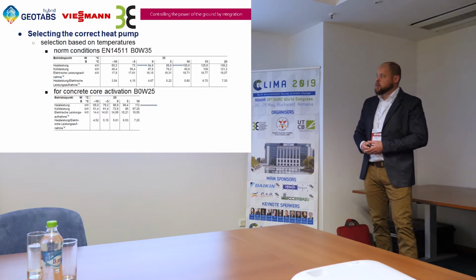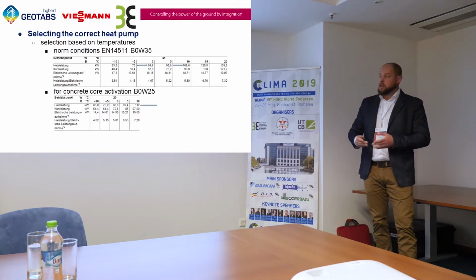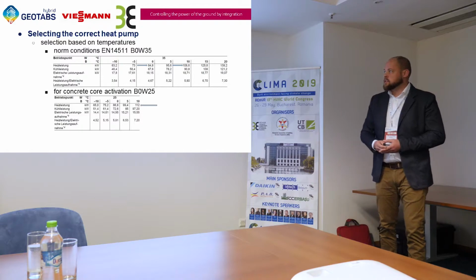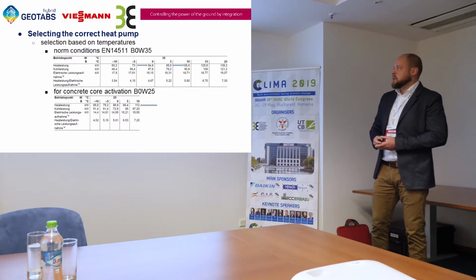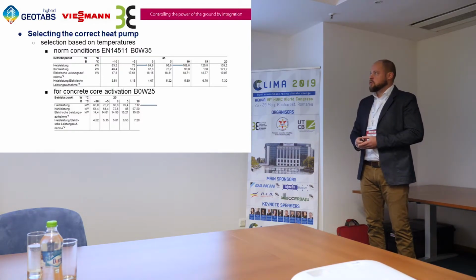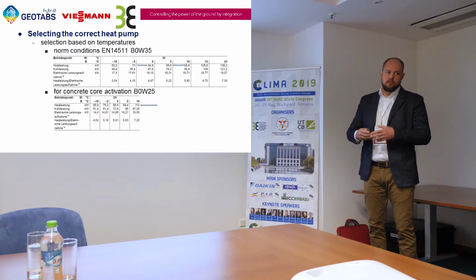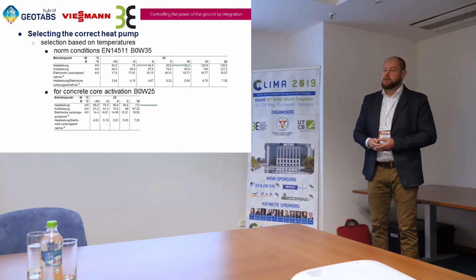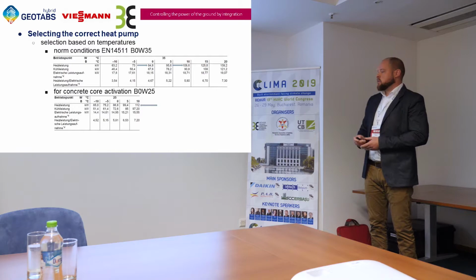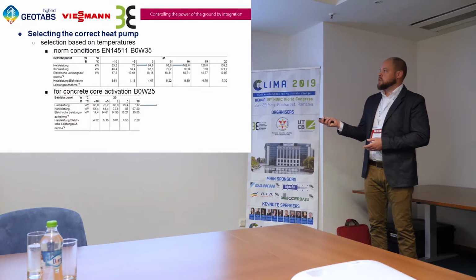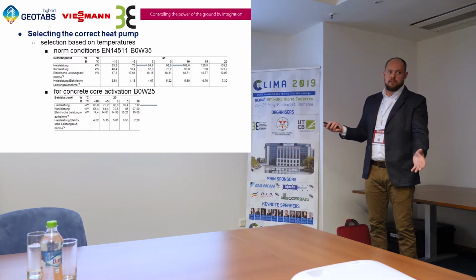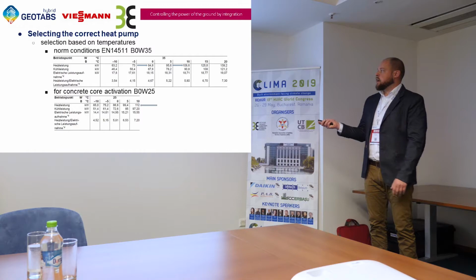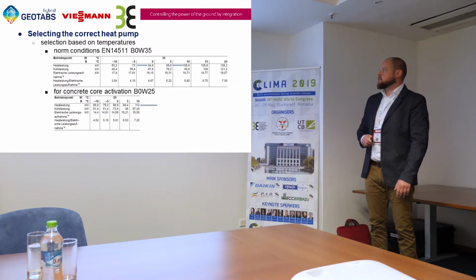Now, how are we going to select the correct heat pump? First, we have to know the building, the size of the building, the heating load, and then it's very important to know the working conditions, because the power output of a heat pump is always given at norm conditions. So that's at the B0 W35, that means that the input temperature to the heat pump is 0 degrees. So out of the source comes 0 degrees, and the output on the secondary side is 35 degrees.